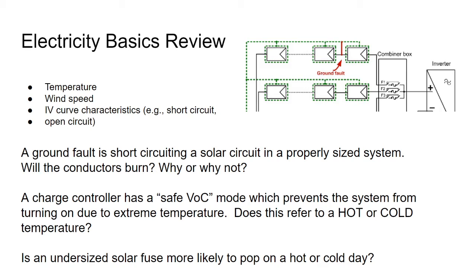because that breaker is tripping off the amperage. And so if the voltage is way high and the breaker is rated for that voltage, your amperage might still be right where it's at on the spec sheet, if not a little bit lower. On a hot, sunny summer day, the amperage may have climbed even though the voltage is down, to the point where that 18, 19 operating amps ekes up to 20 and flips the 20 amp breaker. So when breakers are tripping, there are reasons for it.